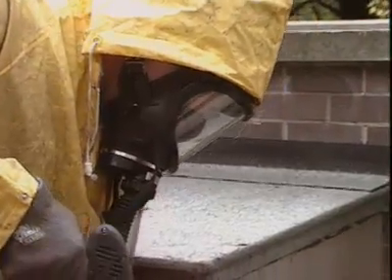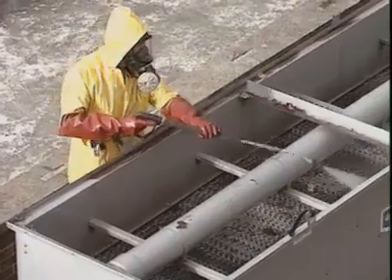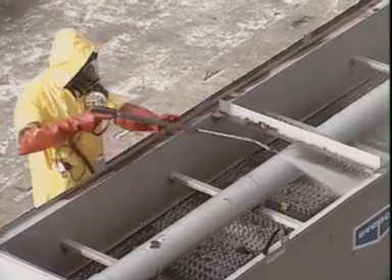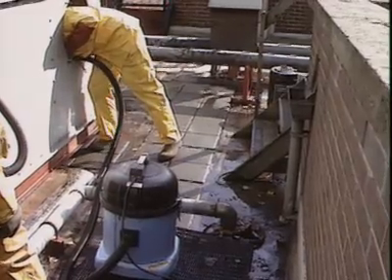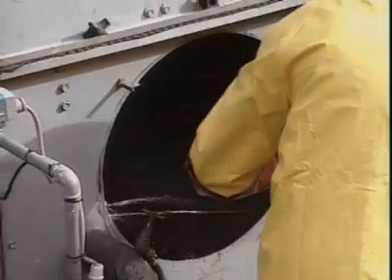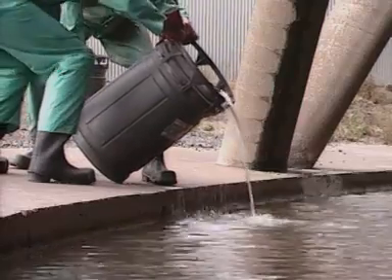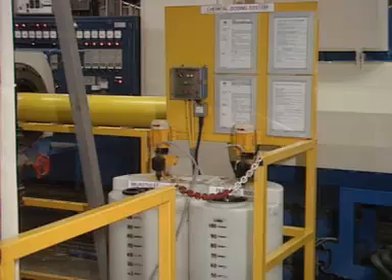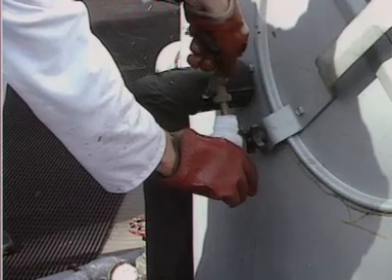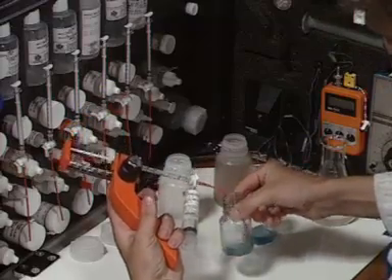Before scrubbing or using a hose, the operator must put on suitable respiratory protective equipment. Then everything is cleaned to remove sludge, scale, rust, biofilm and debris. Cleaning is done twice a year, or more frequently on particularly dusty industrial processes. On a regular basis, chemicals are added, either manually or automatically, to ensure the continued safe running of the system. Tests are performed to monitor the water quality and levels of chemicals and bacteria.